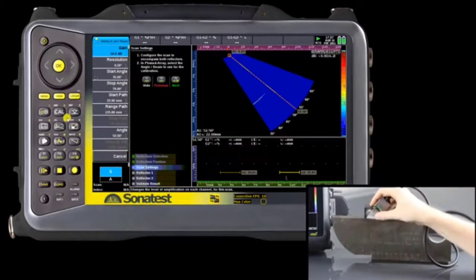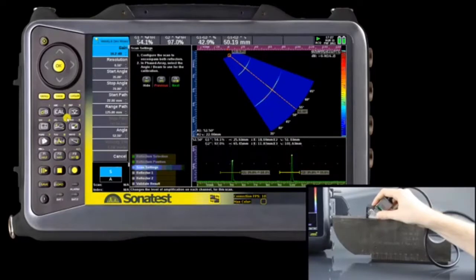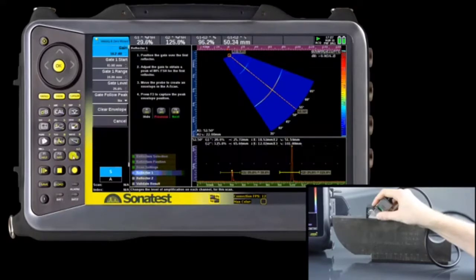The manipulation for this calibration can be done with the block lying on its side. This configuration normally helps to stabilise the signal. For more accurate results, it is recommended to make the calibration with an unsaturated signal. Once both radii echoes appear, we can maximise them and record the maximum value within the envelope. If you make a mistake, use the clear envelope option and start again. Once the envelope has recorded the maximum signal response, adjust both gates over both reference radii echoes.